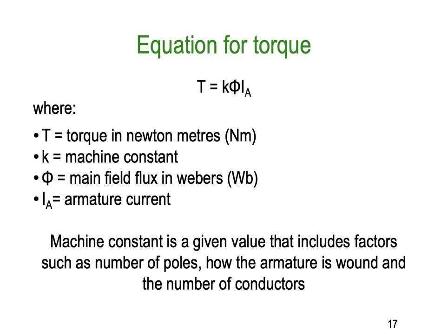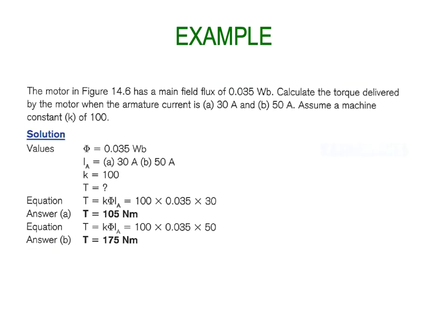The machine constant k is a value that includes factors such as the number of motor poles, how the armature is wound, and the number of conductors — it's built into the manufacturing process and is always a given. Example: The motor from figure 14.6 has a main field flux of 0.035 webers. Calculate the torque when the armature current is (a) 30 amps and (b) 50 amps, assuming a machine constant of 100.